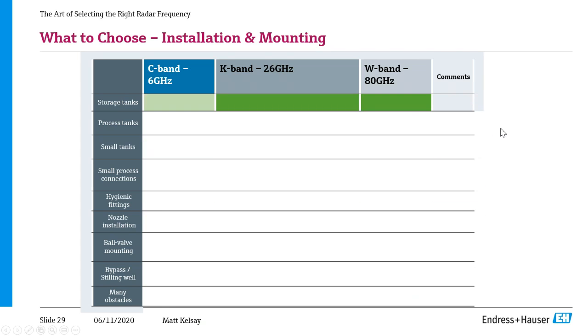For storage tanks, if you click, really just about any device is going to work in a storage tank. These are simple applications where you don't have an agitator. There's not a whole lot going on in the vessel. We list the higher frequencies as better just because of the smaller beam angles. There's less commissioning that you have to do from interference from the sidewall or anything like that. Next, in process tanks, again, your higher frequencies are probably going to be better. Mainly the consideration here is that in process tanks, you're likely to have a lot more obstacles in the tank. So having a small beam angle is going to make that commissioning a lot easier.